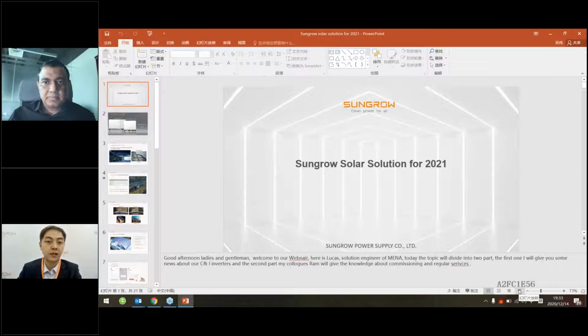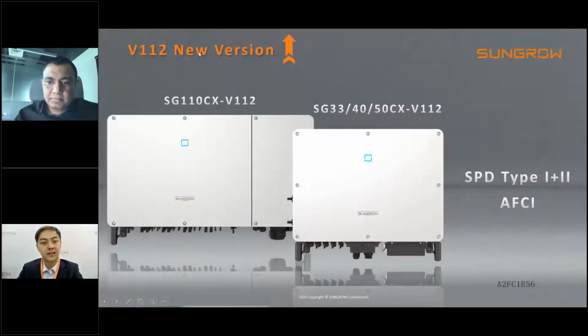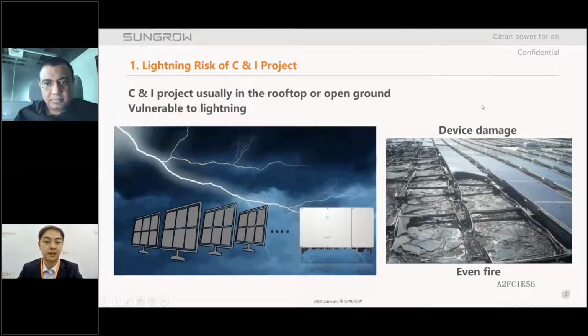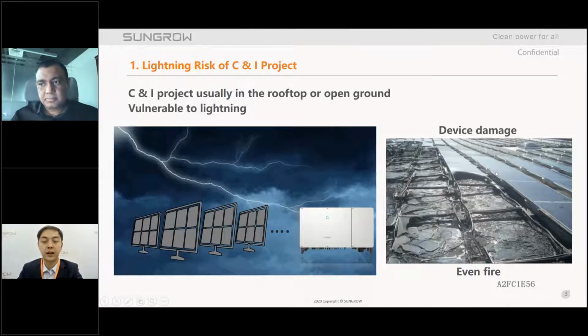As we all know, C&I projects are usually installed on rooftops or in open ground, so they are very vulnerable to lightning strikes directly to the inverter. For this kind of inverter, lightning protection is quite important. Lightning can cause big damage to the plant, even a big fire. So to update the lightning protection, the V112 version of our CX series now updates to type 1+2 SPD on the DC side.